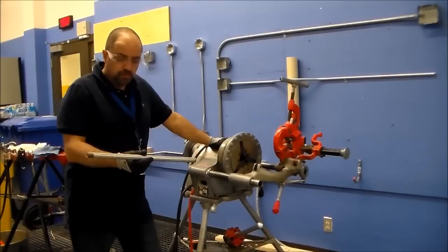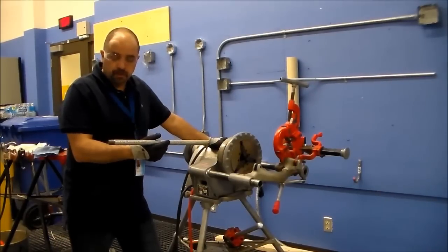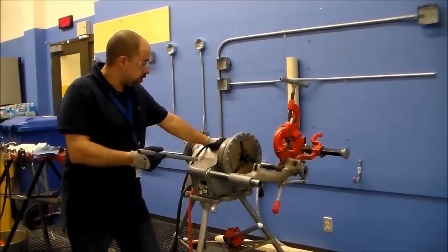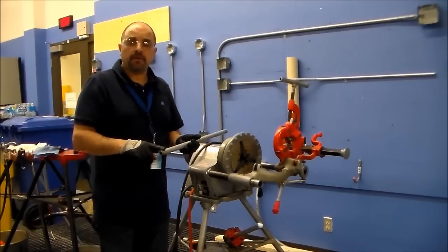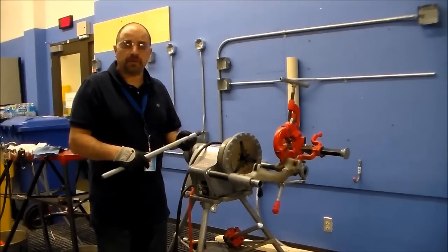Today's lab will be learning how to put a thread on a half-inch rigid piece of pipe on one side using the electric threader — the RIDGID 300 that we have in the shop — and we'll be putting another thread on the other end of the pipe using the hand threader on the tripods.